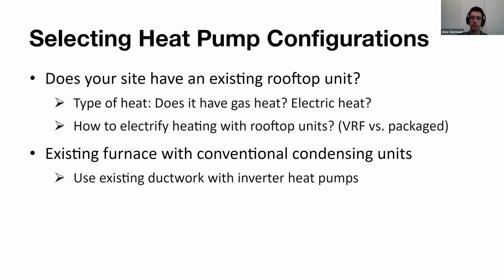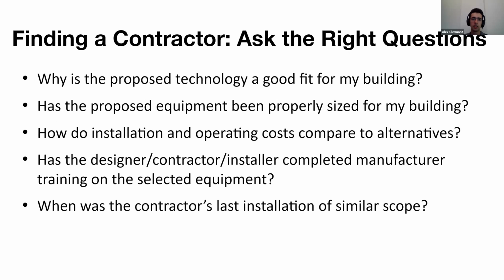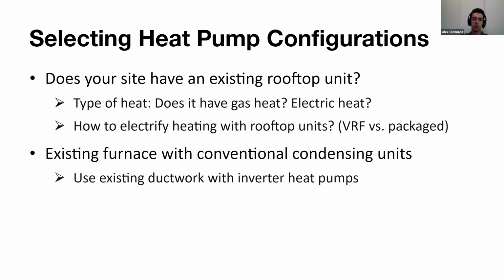Alternatively, we're actually starting to see VRF more commonly used tied to rooftop units as well to electrify that heating. We're starting to see that being used more and more. Now, let's say you do have a conventional condensing unit with a furnace and cooling only coil serving your space, serving your small business. Well, there's actually great options to replace those with completely air source heat pump units, which can do all the heating and all the cooling down to very low temperatures. And there's no issues with that at all. You can actually use the ductwork that's existing as well. It's an option to reuse that existing ductwork to electrify those types of systems. It's quite easy as well.